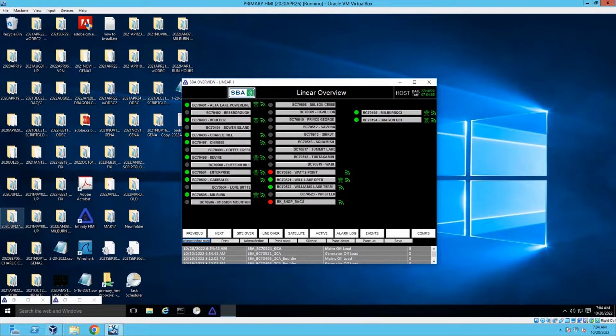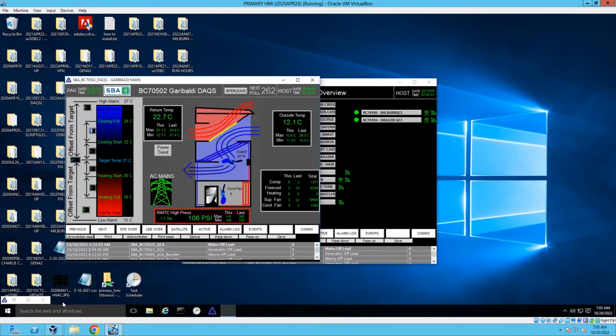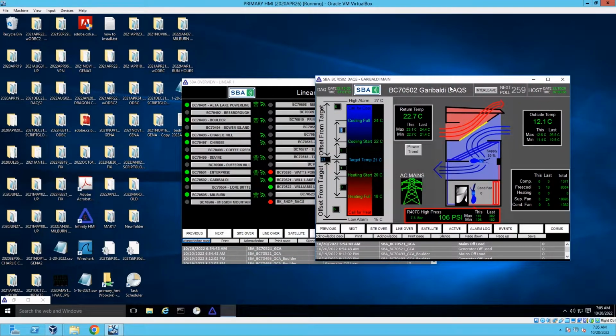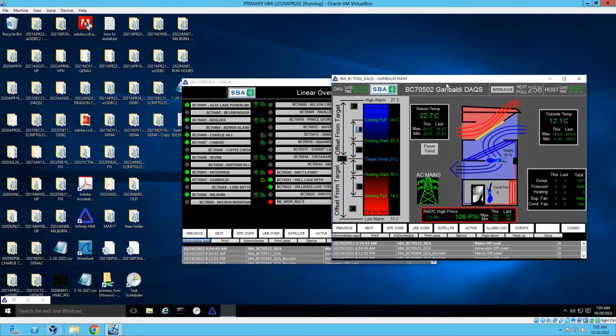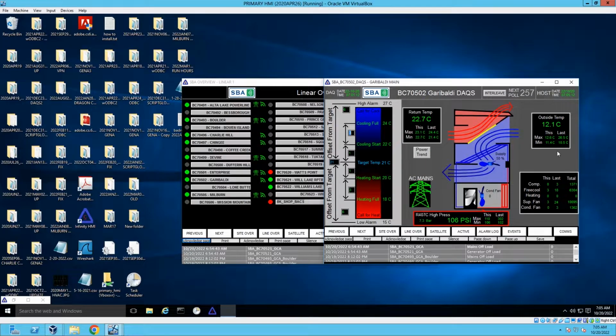In telecommunications sites, environmental controls represent nearly 50% of total power consumption. Free air cooling HVAC units are being implemented that can demonstrate a substantial reduction in power costs and increases in efficiency. When deploying new technology, it is recommended to carefully analyze the first installations until the technology is satisfactorily proven. In some cases, we have been deployed to monitor DAQS free air cooling HVAC units and to complete a cost-benefit analysis. We will look at one such screen.